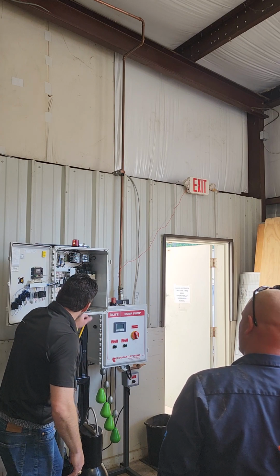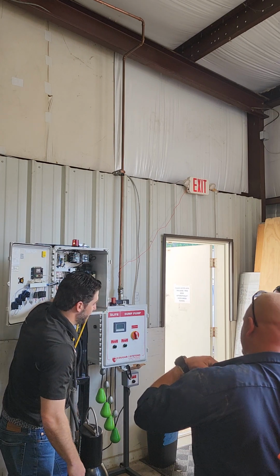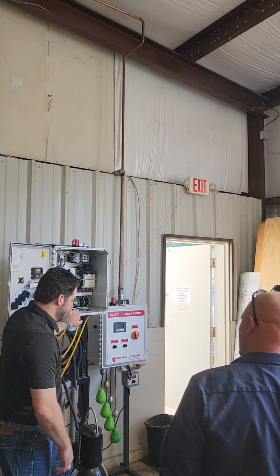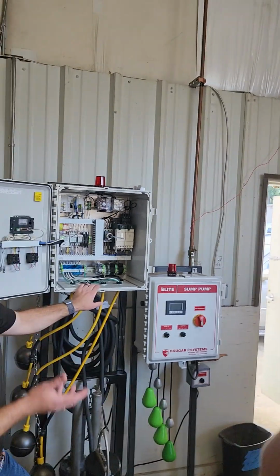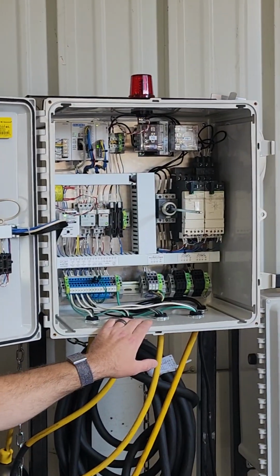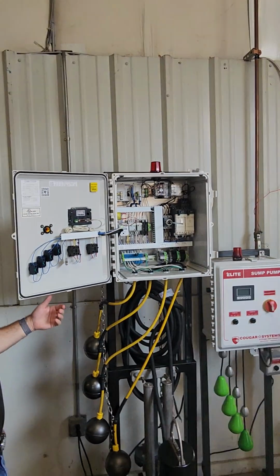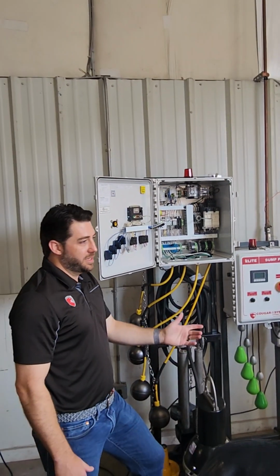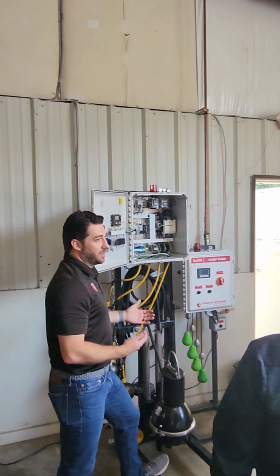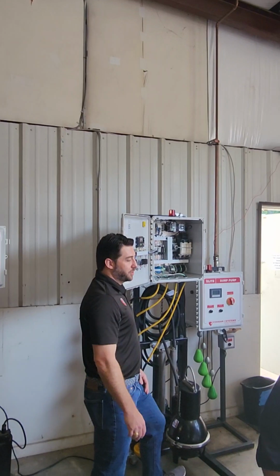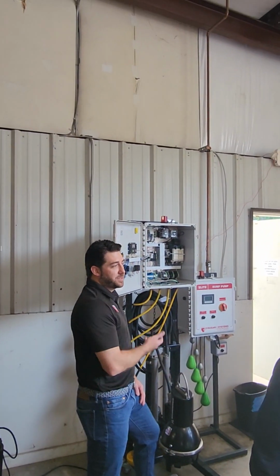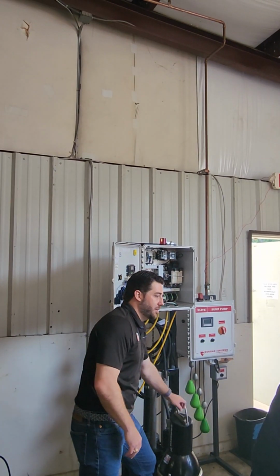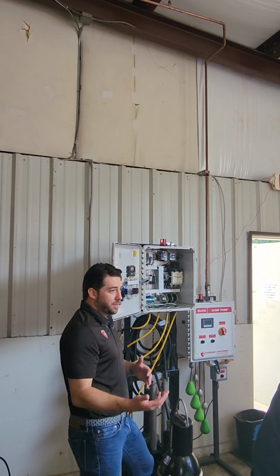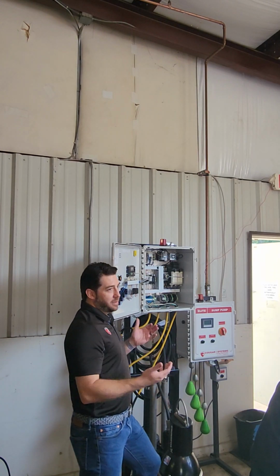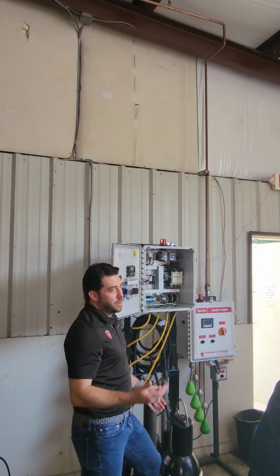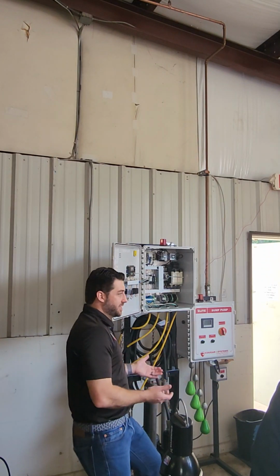The seal fail, in this case, is a conductivity relay, so it's measuring the conductivity through a little sensor in the motor, basically how much water is past the seal. And seal fail is kind of a tough one. I don't know what y'all's company policy is on getting the seal fail, and Jake can probably talk to this too, but it can be a nuisance alarm. It can fail, but it also could be a legit seal fail alarm while the pump is still working. With 10 horsepower and under, the cost of a repair, pulling it and taking it somewhere to get repaired, can be as much as half the price or more of a new pump. So whether or not it's worth it to pull it to see if it really is a seal fail and then repair it.